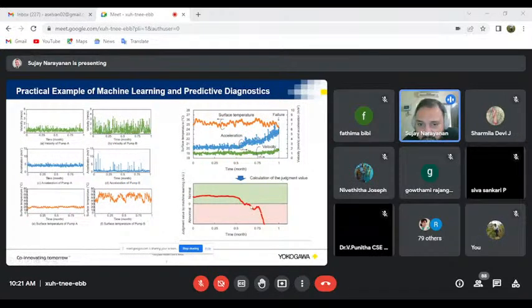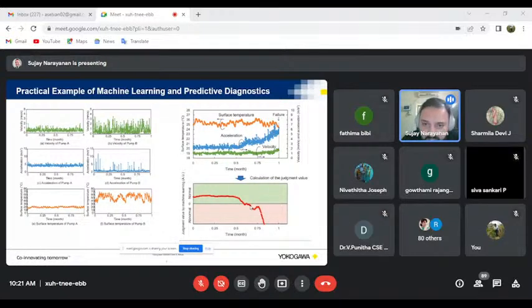Once the pump comes into the abnormal zone, the operator can be notified well in advance to take a proper shutdown procedure, and he can intimate the production that the pump is going to fail. Please allocate your production accordingly. We are going to replace the pump and we are going to have 2 hours of outage time. Give us 2 hours. So they can plan well in advance.